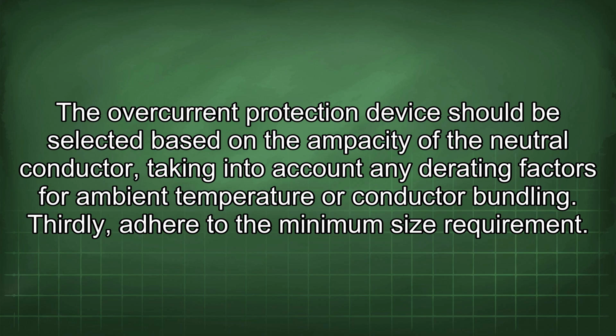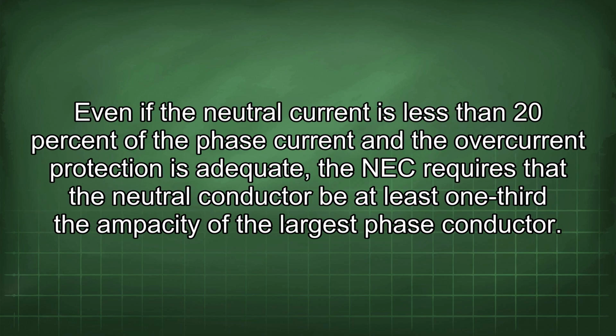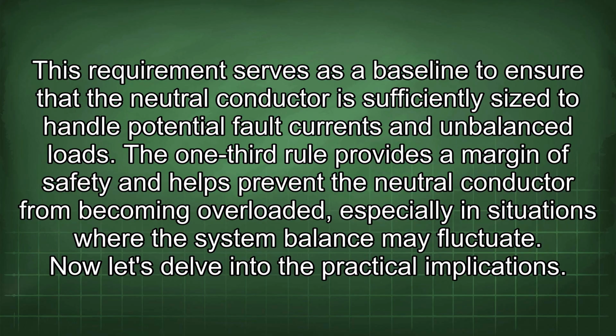Thirdly, adhere to the minimum size requirement. Even if the neutral current is less than 20% of the phase current and the overcurrent protection is adequate, the NEC requires that the neutral conductor be at least 1/3 the ampacity of the largest phase conductor. This requirement serves as a baseline to ensure that the neutral conductor is sufficiently sized to handle potential fault currents and imbalanced loads. The 1/3 rule provides a margin of safety and helps prevent the neutral conductor from becoming overloaded, especially in situations where the system balance may fluctuate. Now let's delve into the practical implications.